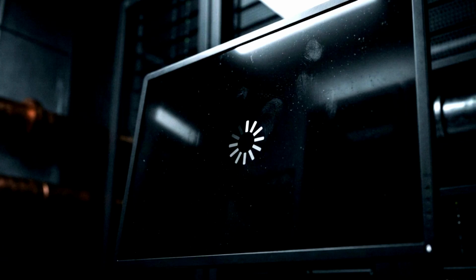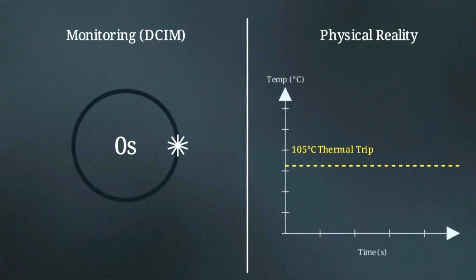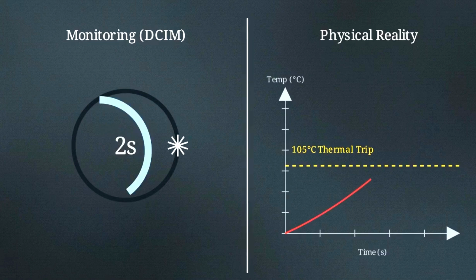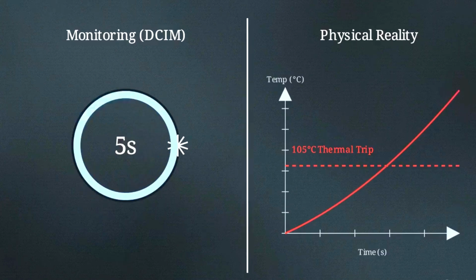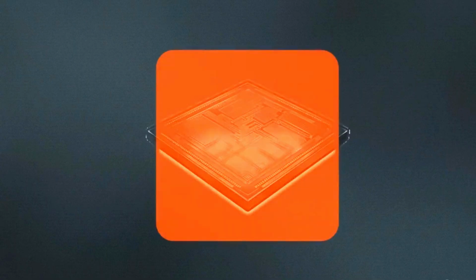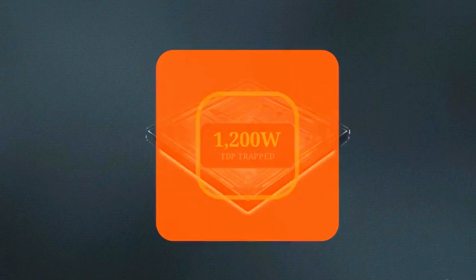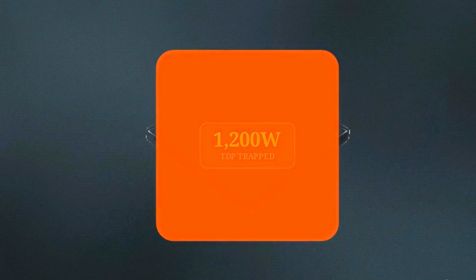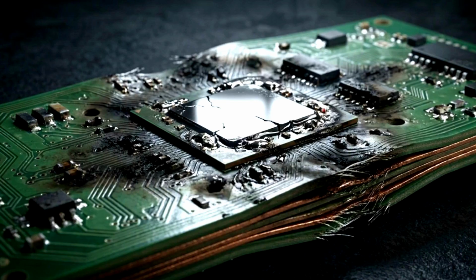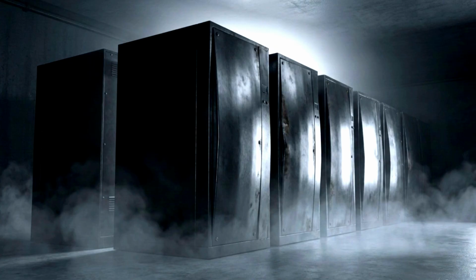The monitoring software was the next failure point. To save processing bandwidth, the management system pulled temperatures only every 5 seconds. In thermal runaway, silicon heats up 15 degrees per second. This 5-second gap allows hardware to melt before alarms trigger. Boiled fluid forms a vapor blanket over the GPU die, trapping 1,200 watts of energy directly inside the silicon. By the time the emergency power off triggered, the GPUs were already destroyed. The degraded UPS batteries buckled under the load, failing to provide the clean shutdown required to save the data.